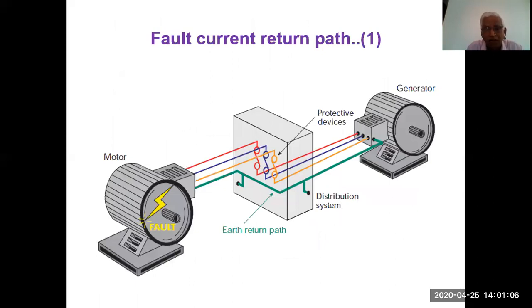Now, fault current return path, case 1. I have shown here a generator, a distribution system, and a motor, and the motor is drawing its supply from the generator. A body connection is also given to all three. That is the green wire, which says the body is connected to all, right? That is one situation. So in case there is a fault in the electrical motor, the current comes through the phase and returns through the ground wire, that green wire. As the circuit is closed, heavy current flows and one of the fuses will go.